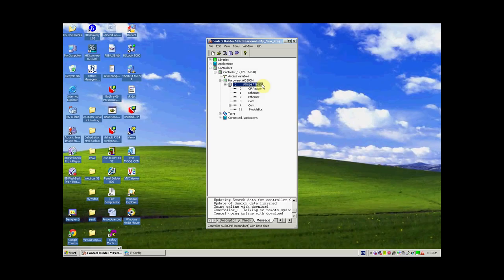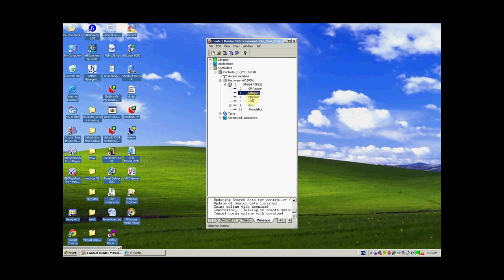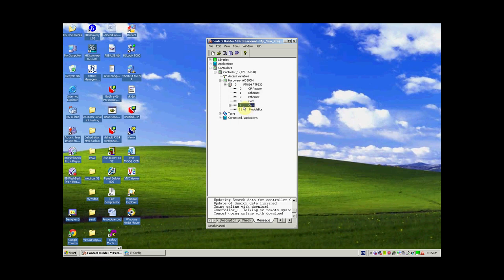After selecting the PM864 controller, we can see there are four ports: the CF reader for installing external flash to increase internal programming memory, two ethernet ports for communicating with the PC after configuring the IP, and two COM ports for serial communication. First we are going to use COM4, the tool port, to communicate with the AC800M controller when it is first unboxed, so we can assign an IP address on the CN1 and CN2 ethernet ports.